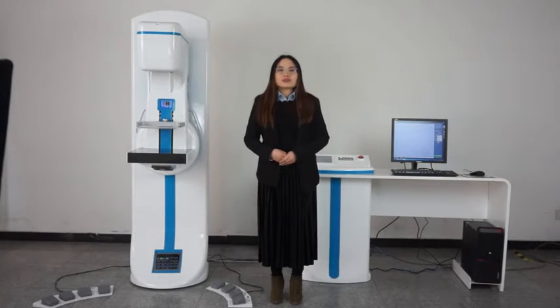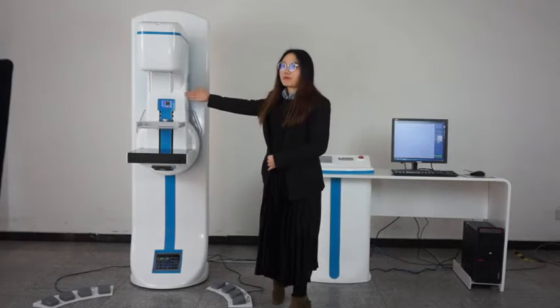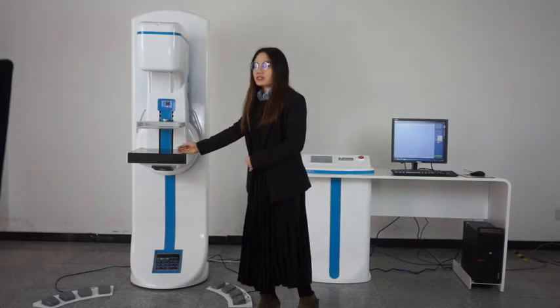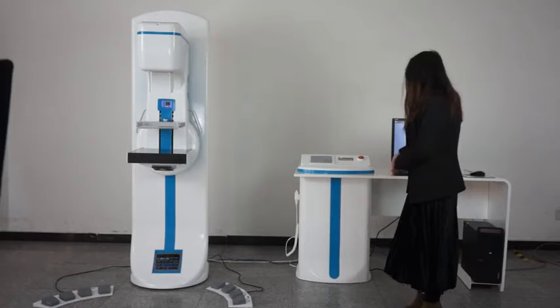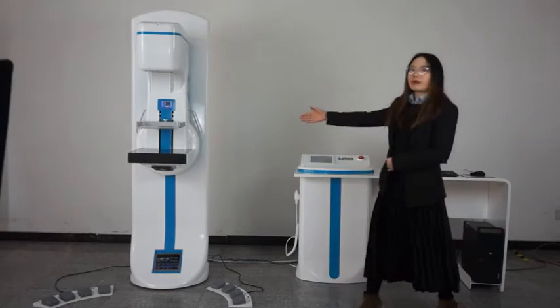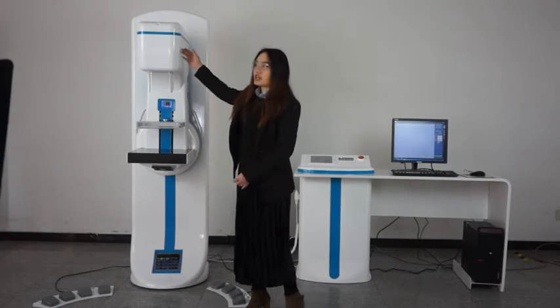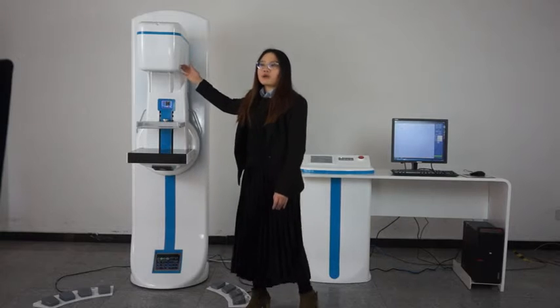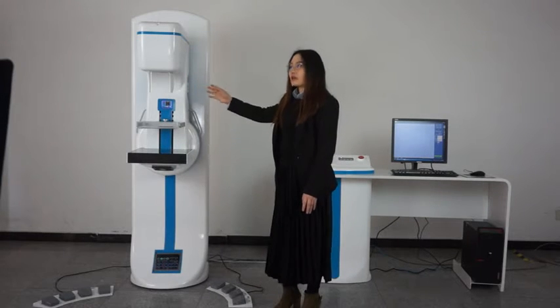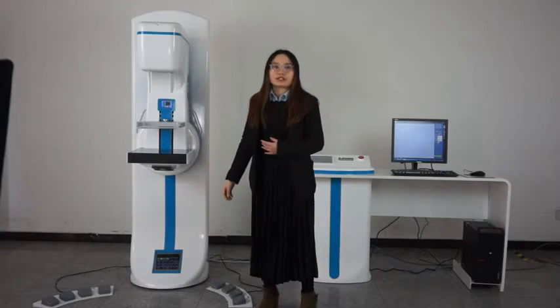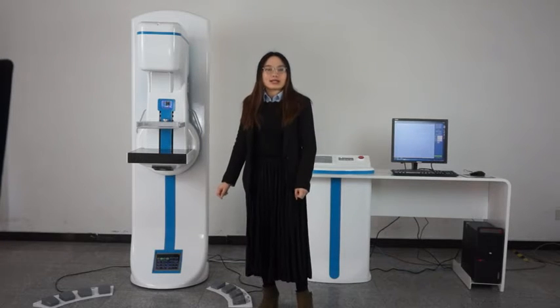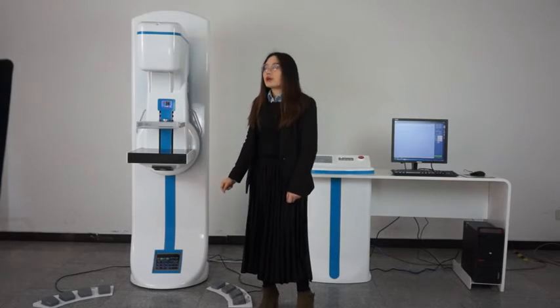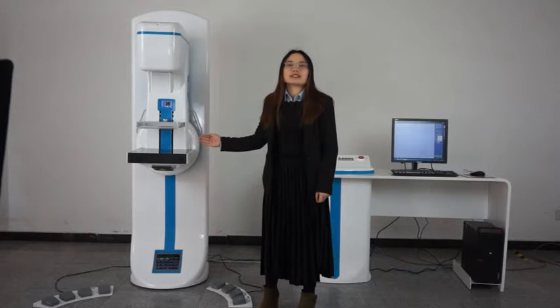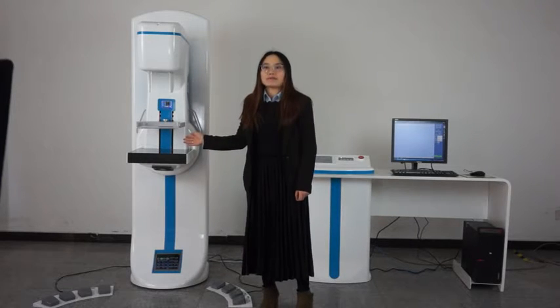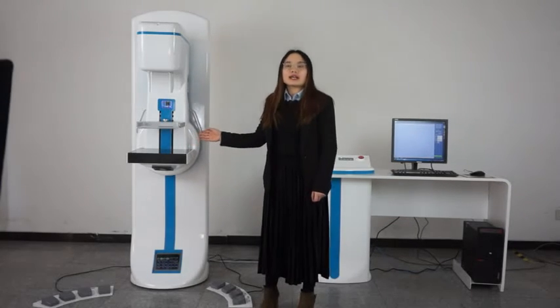Okay, let's look at the structure of the machine. It is composed of the X-ray mount block, flat panel detector, control console, and digital workstation. Here is the big nose, the combination of the generator and X-ray tube. What I want to emphasize is our exclusive workmanship of the generator, a solid-state quasi-resonant high-frequency generator. We are the first factory to acquire this kind of technology. It is supported by the Ministry of Science and Technology Innovation Funds.